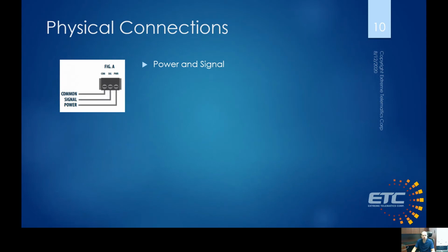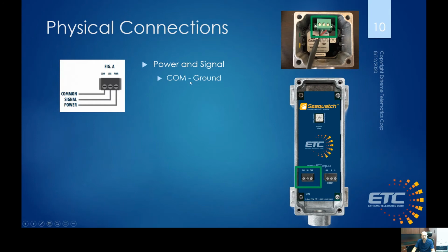As for physically wiring the Cyclops or Sasquatch, they both have the same power and signal connector. So you can see here we've got COM, SIG, power. COM is common or ground. That's going to be attached to the ground of your controller. SIG is a dry contact output, and we'll talk about that more on the next slide. But basically, SIG is shorted to ground or common, and so we complete the circuit when the plunger arrives. So normally it's open, and then we close it on arrival.